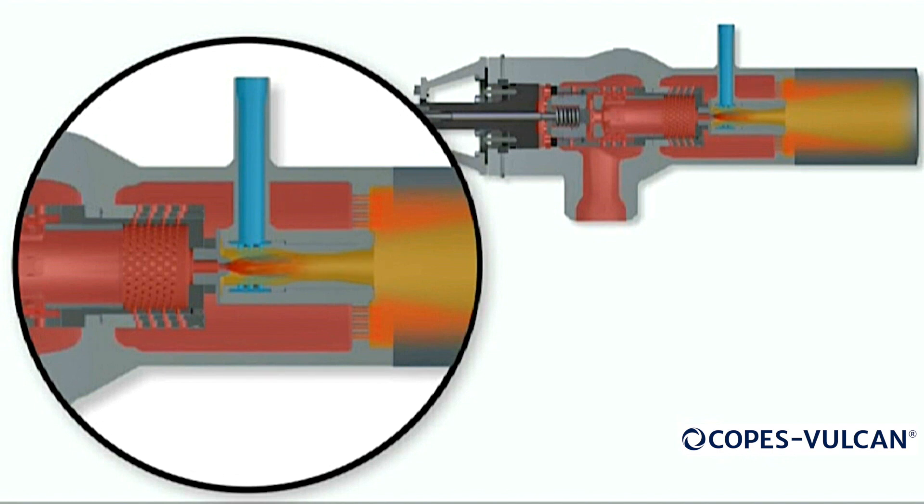Mechanical spray nozzles also rely on the surrounding steam velocity to provide adequate mixing. When the steam load reduces, so does the steam velocity and the ability of mechanical spray nozzles equally reduce. This effect manifests itself with poor downstream steam temperature control and water dropout.